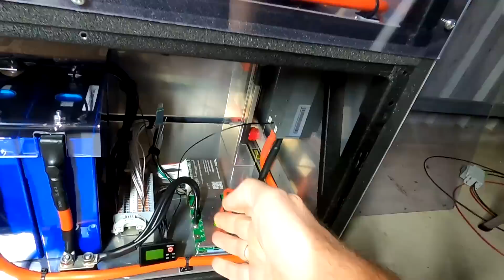The circuit breaker here only disconnects this main unit from the other battery banks. That's why I have this order: circuit breaker, BMS, battery, and not the other way around. Because in case of a fault, you turn off the circuit breaker and the BMS is on the other side, so it won't talk to your batteries anymore, and you have no idea what's going on with the batteries. If one cell is peaking or has an issue, you'd have no idea unless you measure all the cells manually with a voltmeter. From a maintenance perspective, it's far more convenient to have the BMS still connected to the battery. Yes, the BMS uses a few milliamps of power, but with these large battery cells it is not an issue.